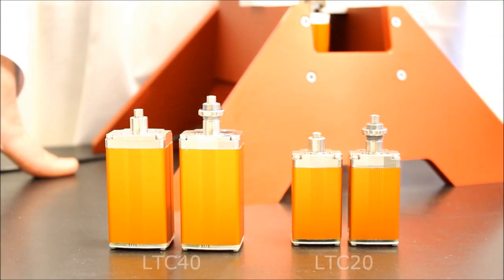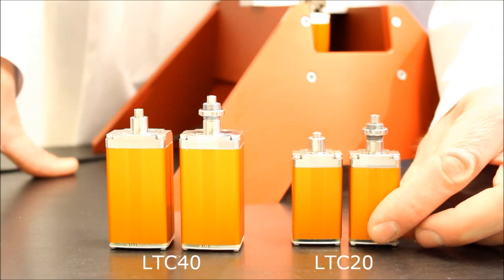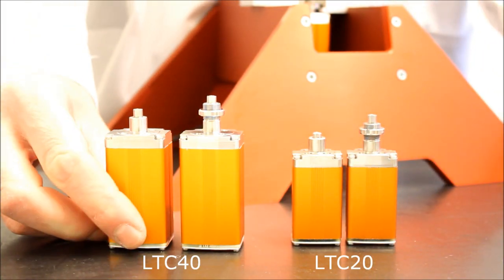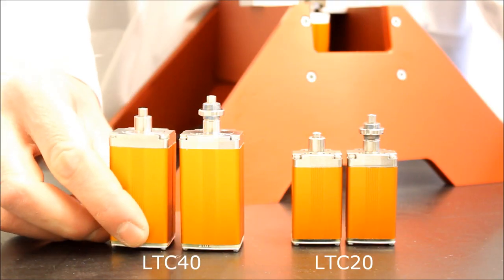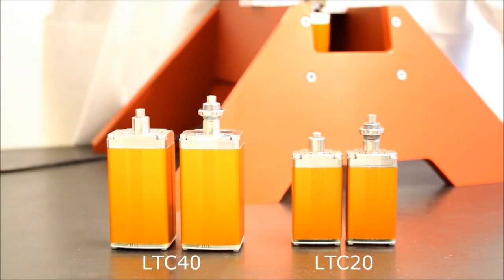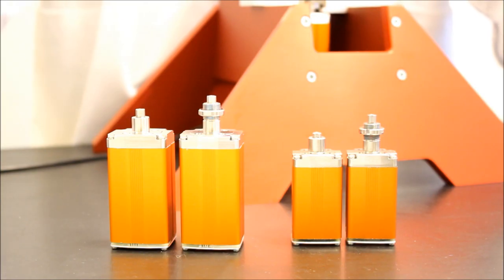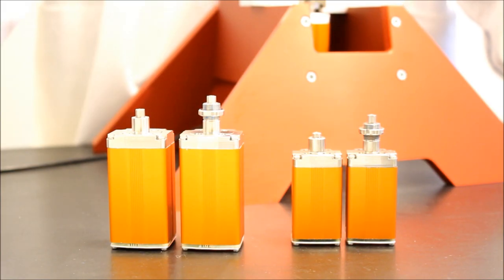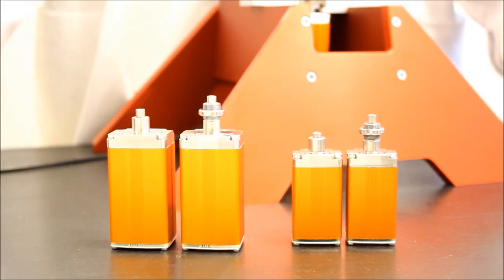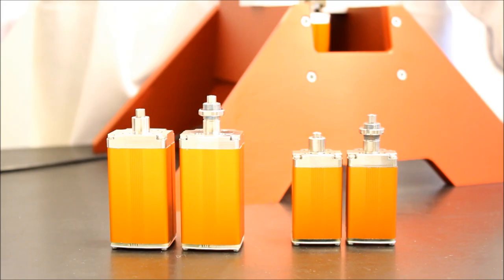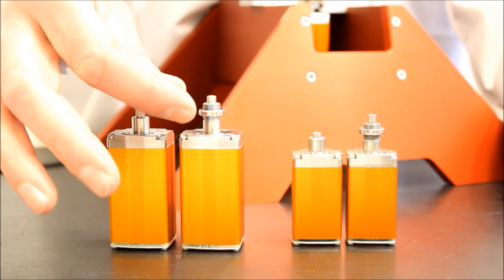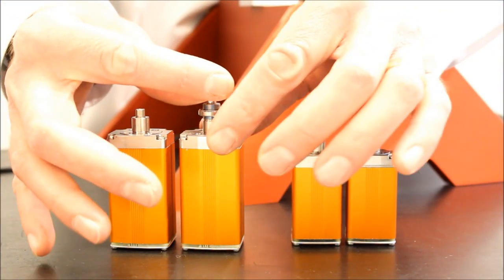I will demonstrate the PiezoLEGS technology live using the LTC20 and LTC40 linear motors, rated to 20 and 40N stall force. These motors are enclosed versions of the OEM motors, with standard clamp mount or nut mount. The driveshaft is guided and has a threaded hole to fit an end piece, for example a hard ball tip.